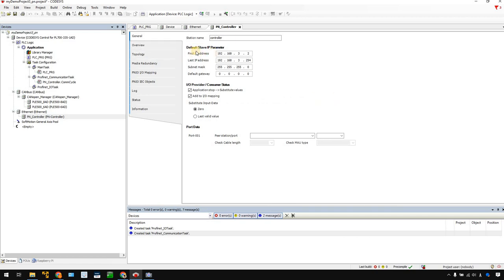First of all, you need to set your first slave IP parameters. If you've seen my previous Profinet tutorials, you will know. The Profinet IO controller assigns IP addresses to each Profinet IO device based on the device name. So the first slave IP address — if I add a WAGO coupler here, the first address will be x.x.3.2. If I add other Profinet IO devices, they will be .3, .4, .5, and so on.